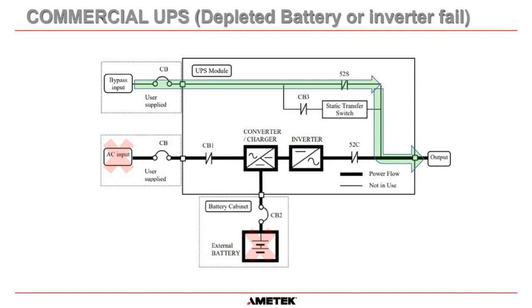The static transfer switch in a commercial UPS is essentially a momentary switch using SCRs. Commercial UPSs underrate their SCRs, expecting them to carry load for only a short time. After a successful transfer, they pull in a contactor so power flows to load circuits through the contactor rather than through the SCRs in the static transfer switch. That is how a commercial UPS works.